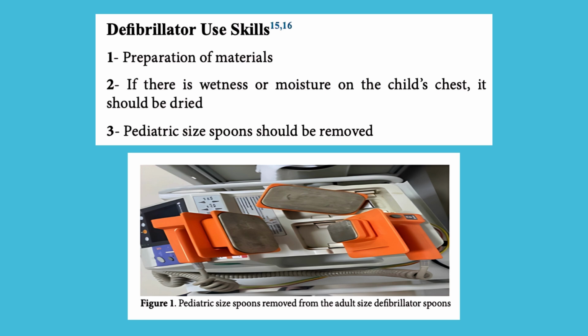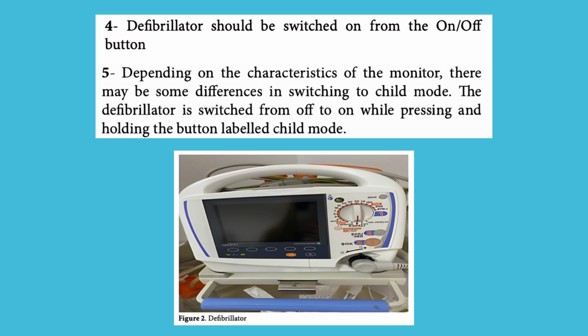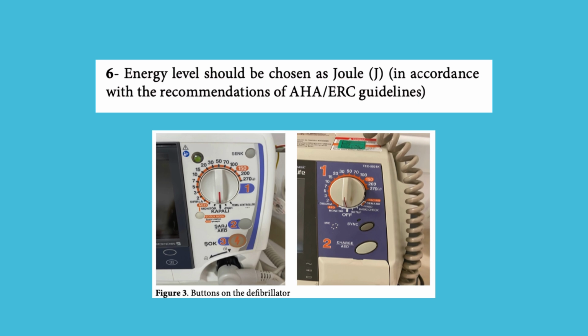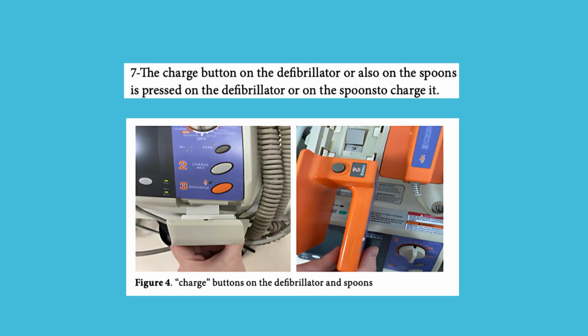Defibrillator use skills. 1. Preparation of materials. 2. If there is wetness or moisture on the child's chest, it should be dried. 3. Pediatric size spoons should be removed. 4. Defibrillator should be switched on from the on-off button. 5. Depending on the characteristics of the monitor, there may be some differences in switching to child mode. The defibrillator is switched from off to on while pressing and holding the button labeled child mode. 6. Energy level should be chosen as Joule, J, in accordance with the recommendations of AHA/ERC guidelines. 7. The charge button on the defibrillator or on the spoons is pressed to charge it.